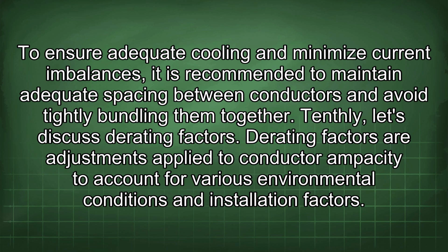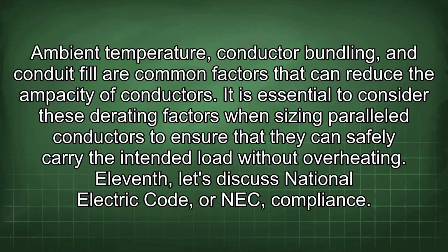Tenthly, let's discuss derating factors. Derating factors are adjustments applied to conductor ampacity to account for various environmental conditions and installation factors. Ambient temperature, conductor bundling, and conduit fill are common factors that can reduce the ampacity of conductors. It is essential to consider these derating factors when sizing parallel conductors to ensure that they can safely carry the intended load without overheating. 11th, let's discuss National Electrical Code, or NEC, compliance.